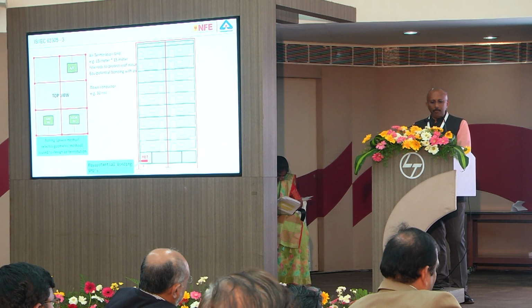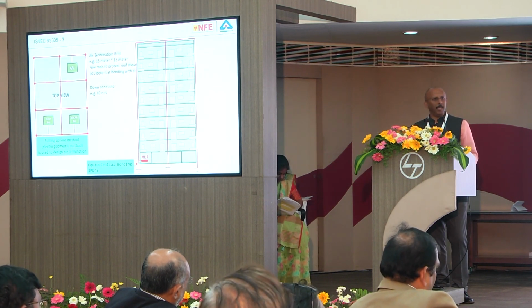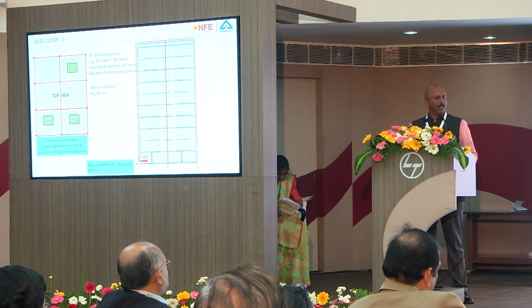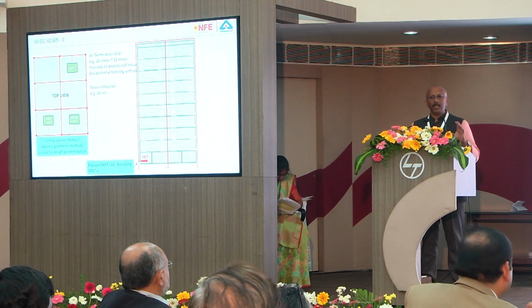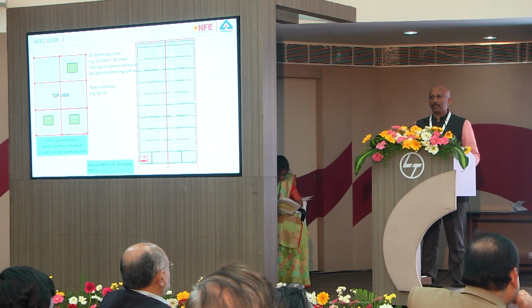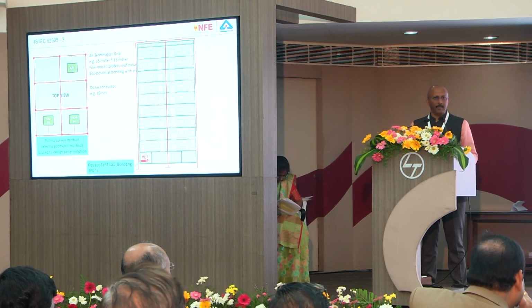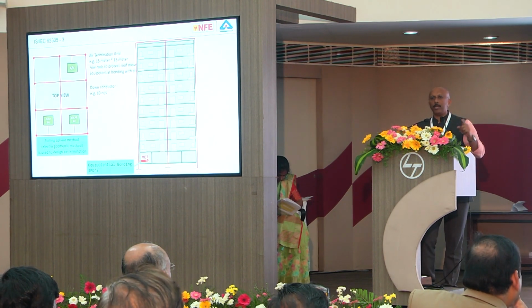Then the fourth subject is that the down conductor must be connected to the protective equipotential bonding of your building. It means at the mains incoming, you have an earth bus bar, the down conductor must be connected to the earth bus bar, and you are also supposed to put devices called SPD, surge protection devices, in these switchboards. Now, you have 10 different metallic objects, like one service going to the street light, another going to maybe something else. So if 10 wires are going out of your building, on all the 10 wires you are supposed to put SPDs and make this kind of bonding.